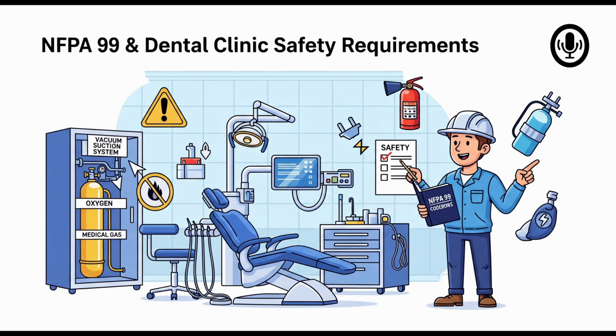They're deemed critical enough, even in a Category 3 setting, that they need an alternate power source that kicks in automatically if the normal utility power fails. This ensures the air supply continues and you maintain awareness of the system status during an outage. What kind of alternate source? Like a generator? It could be a generator or maybe a large battery backup system, UPS, depending on the load and duration needed. Section 6.7 talks about essential electrical systems, EES.